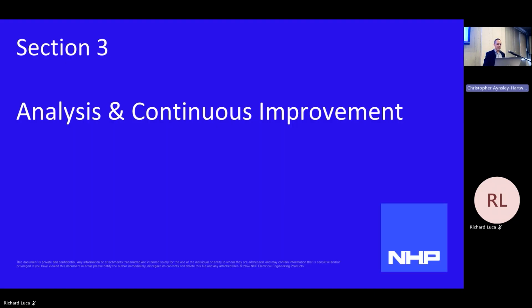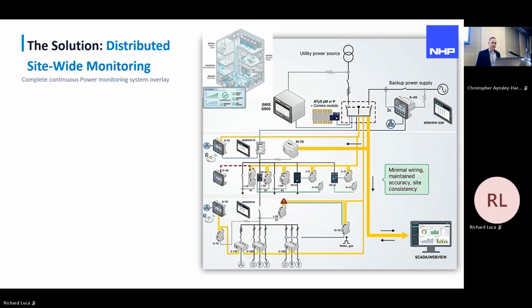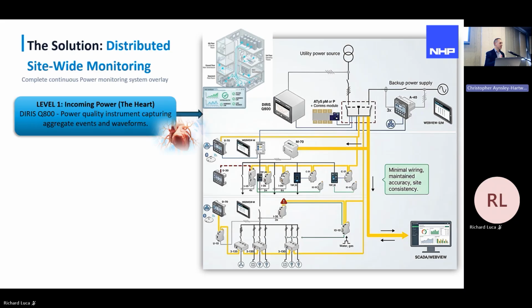So, analysis and continuous improvement. This topology here shows a site-wide power distributed approach where we're monitoring, and seeing as though we're talking about hospitals, I've stuck with the same theme here. So we're calling the level 1 incoming power the heart, right? So using, say, a Q800, it's monitoring for sags, swells, interruptions, events, a class A meter, tested to the standards. You'll be able to see from a site-wide perspective everything that's happening on the network. If there's any anomalies, you can drill down further.